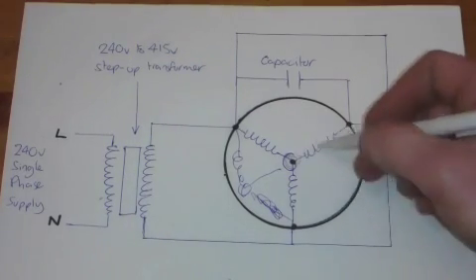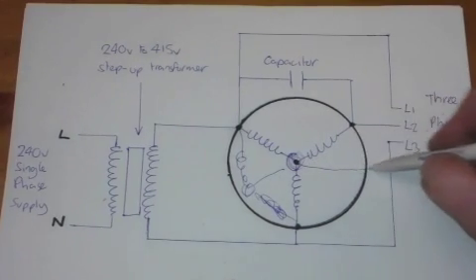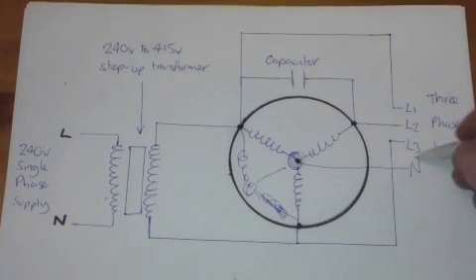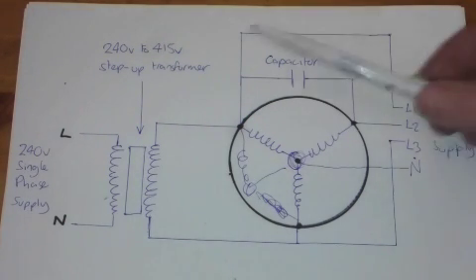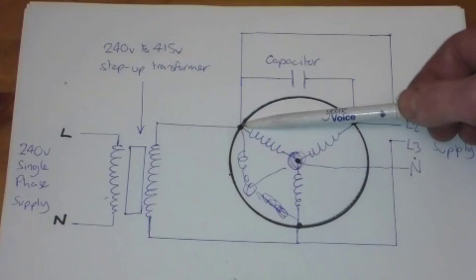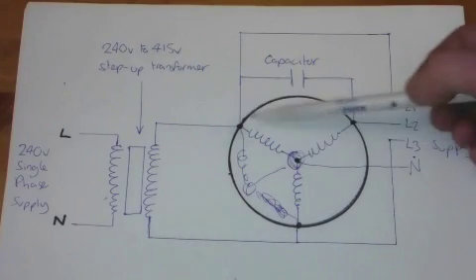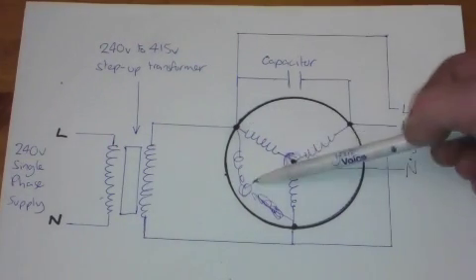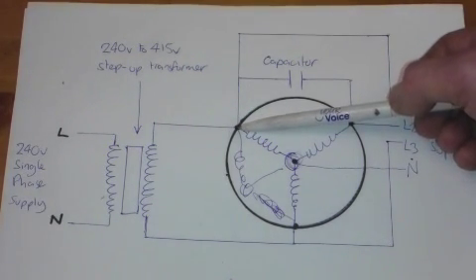If you did tap into neutral there and this is how I was running a phase converter for a short while before I started destroying motors you could tap into that neutral but it would be 240 volts thereabouts above earth and of course as I described in part one this little chap here he's 415 volts above earth that should only be 240 to neutral but because the neutrals not where it should be and it's moved if you touch that phase there that's going to give you a 415 volt shock.